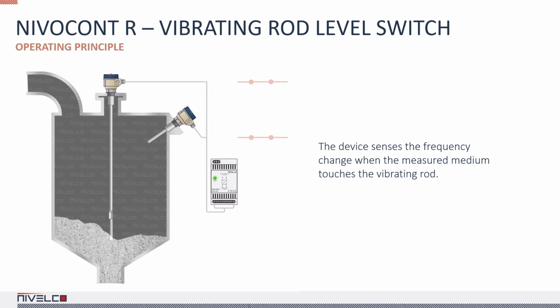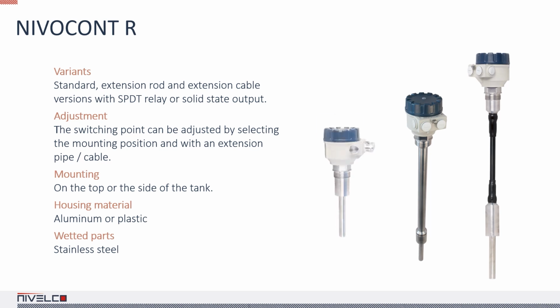When the medium touches the rod, the vibration changes or stops. When the level drops and the medium no longer touches the rod, it starts to vibrate freely again. The electronic senses the change in the vibration and sends out a signal after a predetermined delay. There are numerous options, like an extension rod or an extension cable for the probe, and the output can either be an SPDT or a solid-state relay. The device covers either aluminum or plastic, and the wetted parts are made of stainless steel.